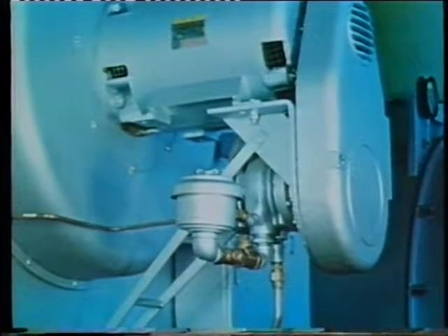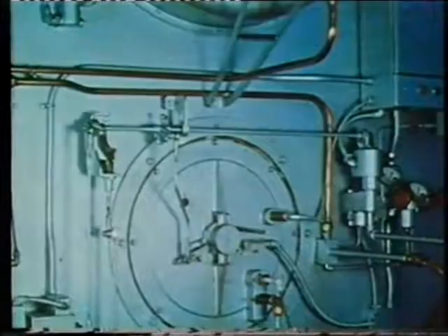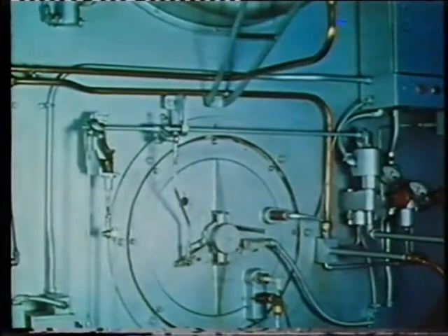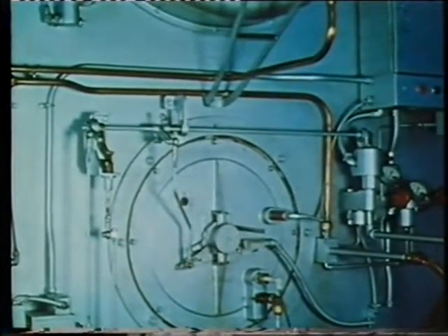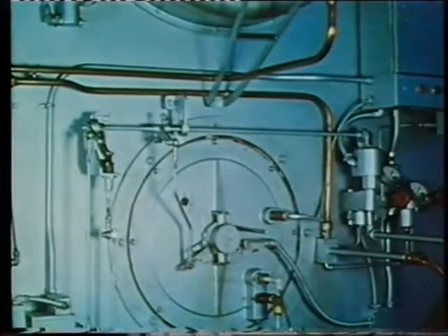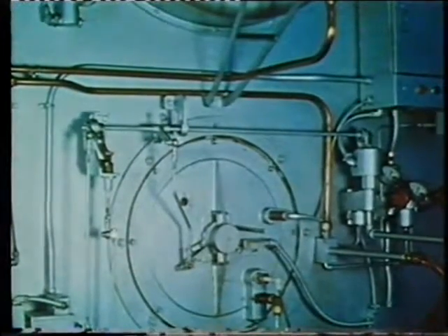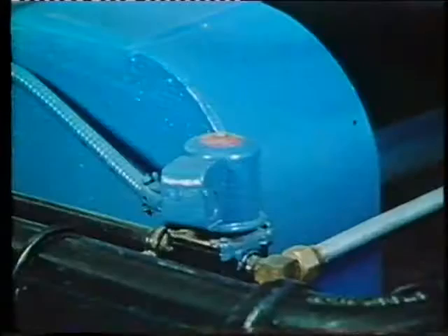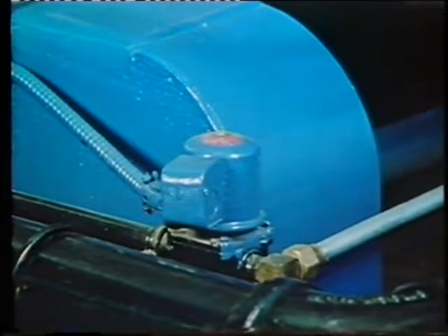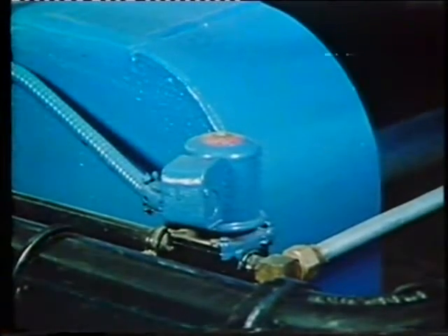At startup, the controller first turns on the secondary air blower. The modulating motor also opens the air damper wide so that air can be blown through the combustion chamber to purge it of any unburned gases. After a timed purge cycle, the gas pilot solenoid valve opens to allow gas to flow to the pilot.